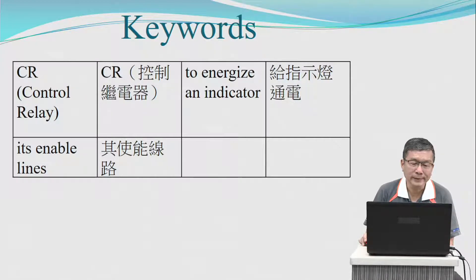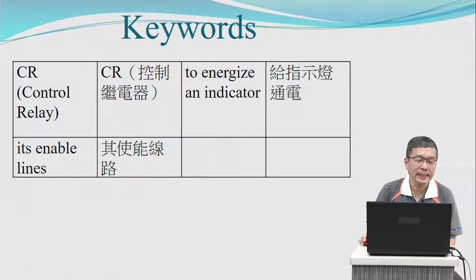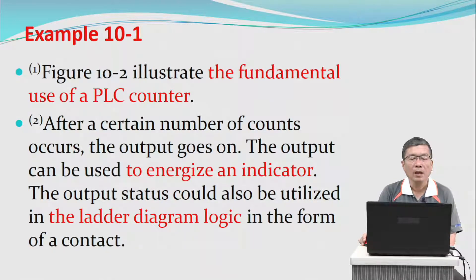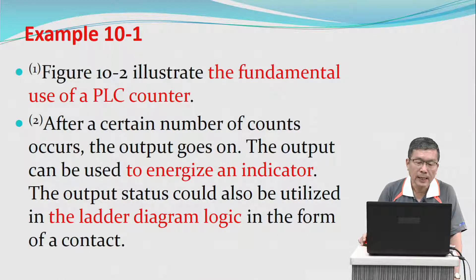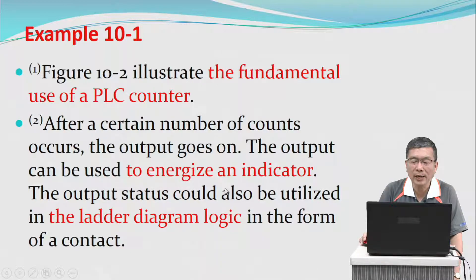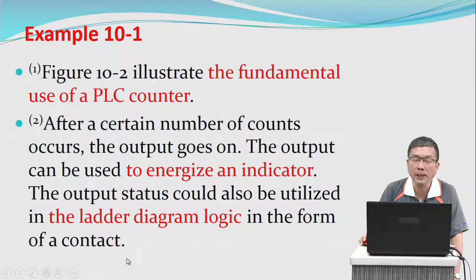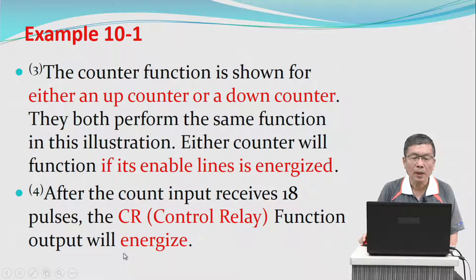A control relay to energize an indicator is enabled. Figure 10.2 illustrates the fundamental use of a PLC counter. After a certain number of counts occurs, the output goes on. The output can be used to energize an indicator, and the output status could also be utilized in the ladder diagram logic in the form of a contact.